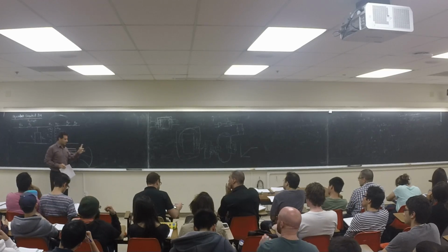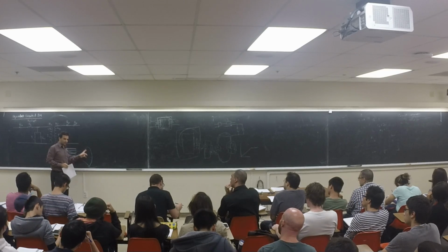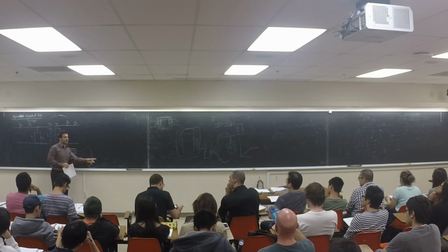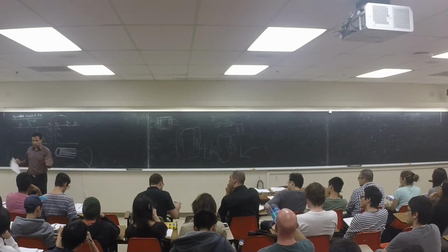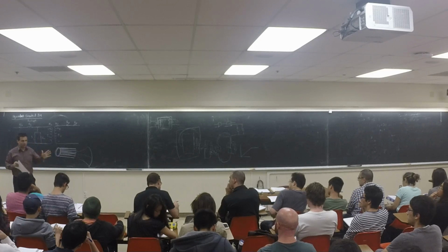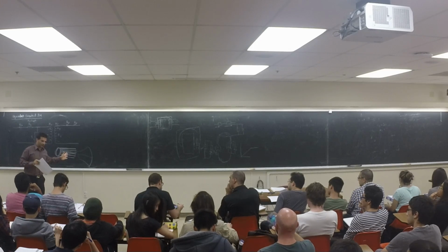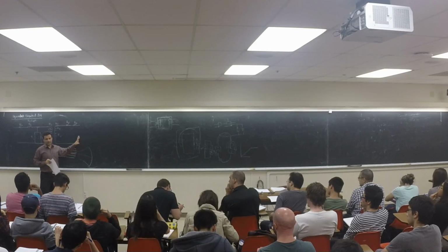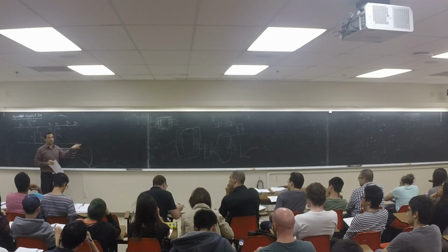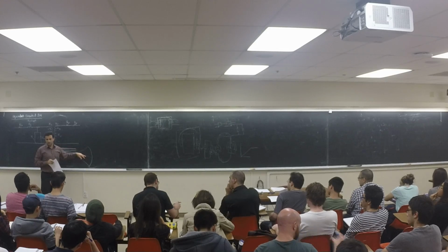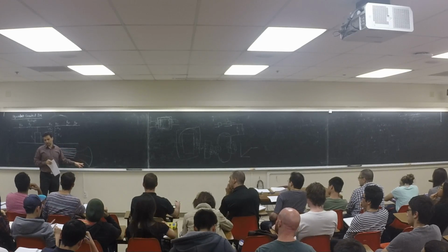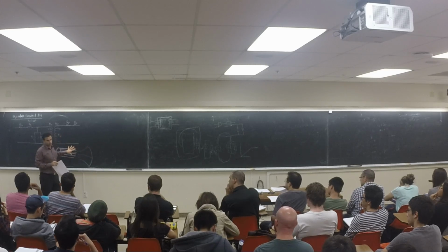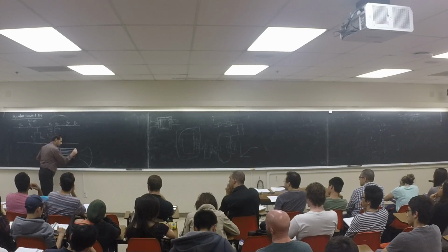if you have access to this one, we will talk about this later. We'll add some resistor here, exactly what we did for the DC machine, to limit the current. And gradually we take that resistor out, exactly what we do. But my point is, at the end of the day, when we get to the steady state, all shorted. We're not going to put any resistor in the rotor winding because it's going to cause power loss. It's going to bring the efficiency down, right? So whether it's a wound rotor or a squirrel cage, it will be shorted.